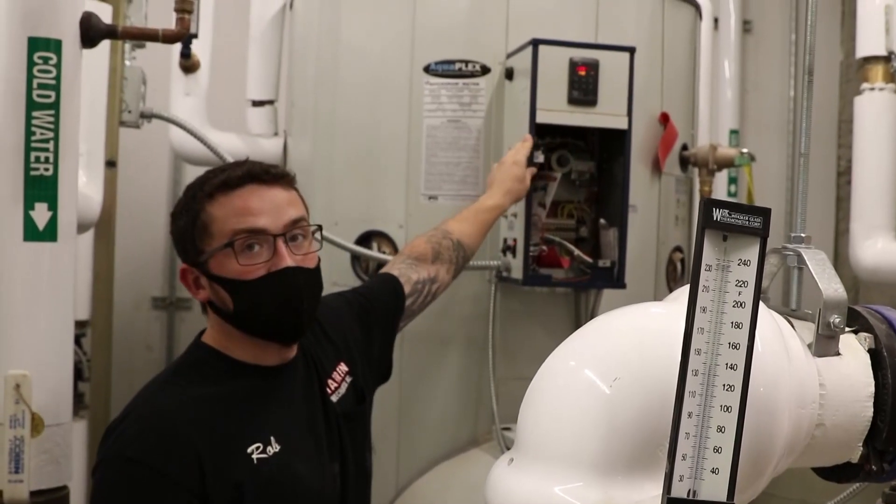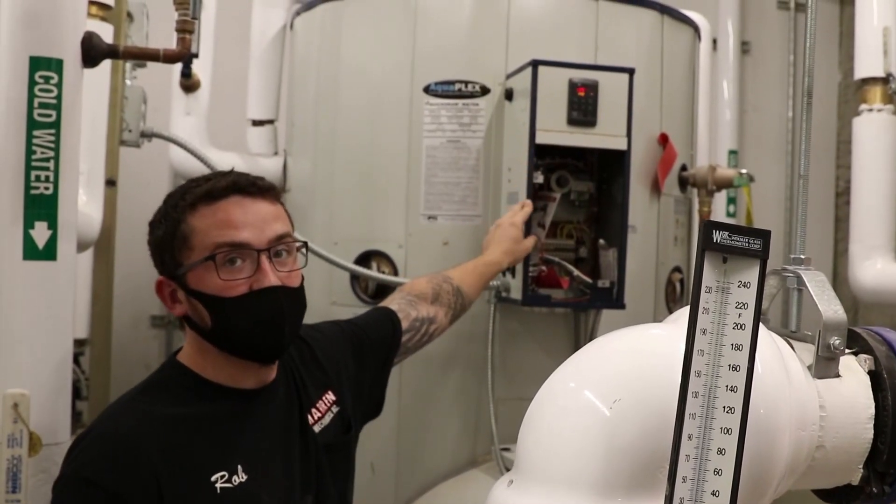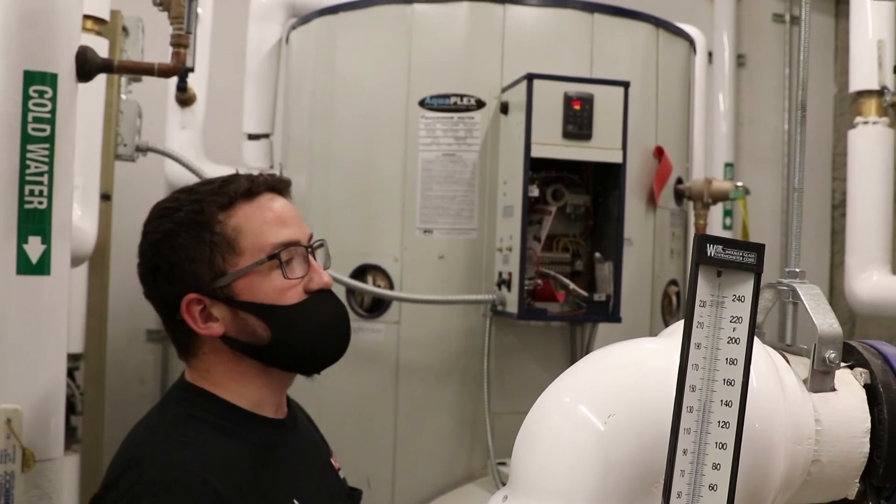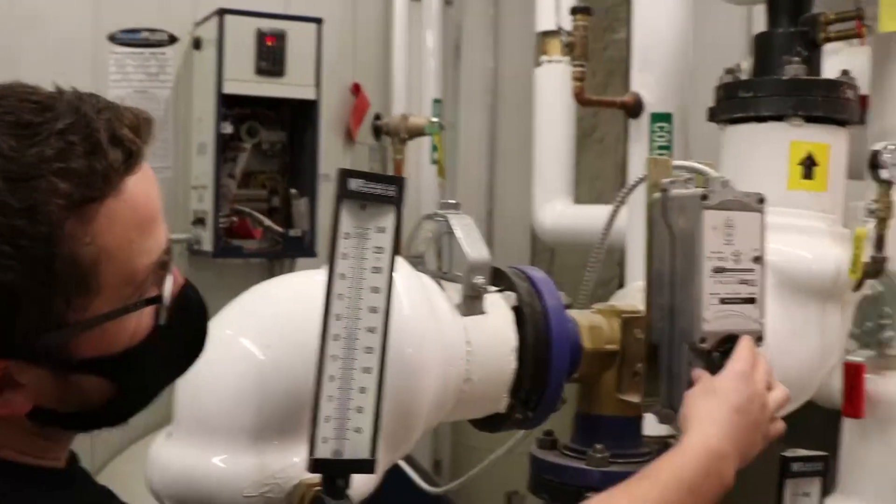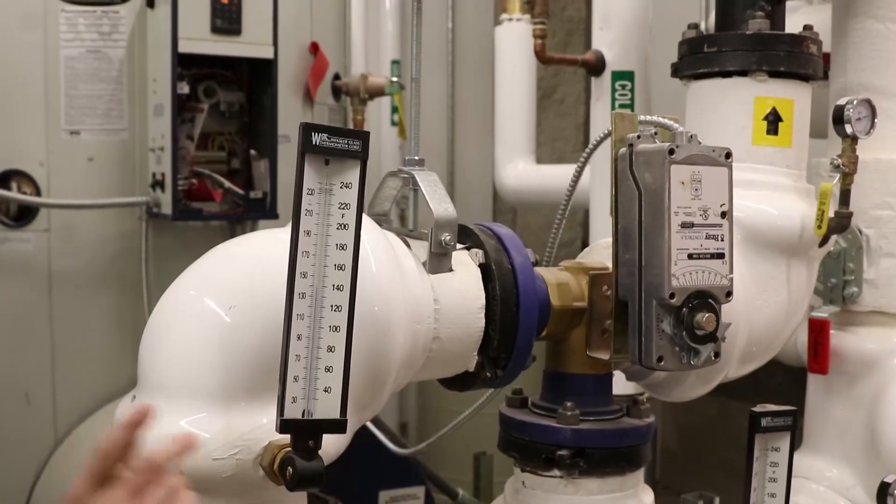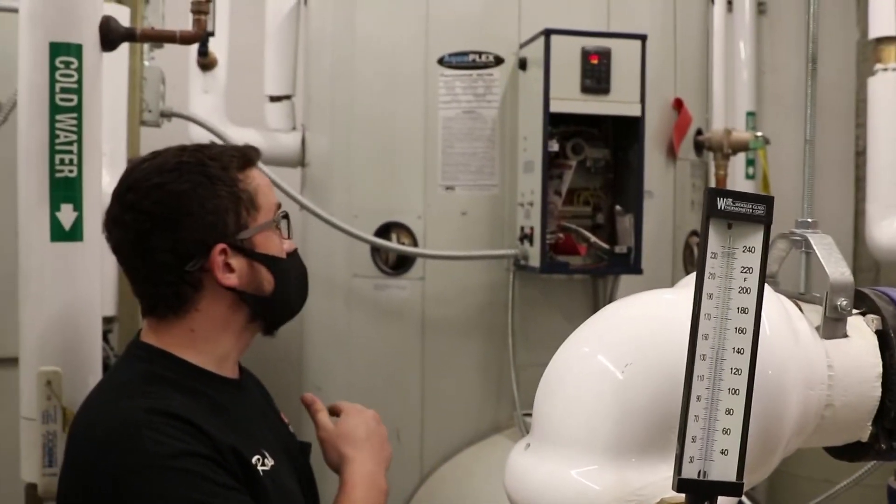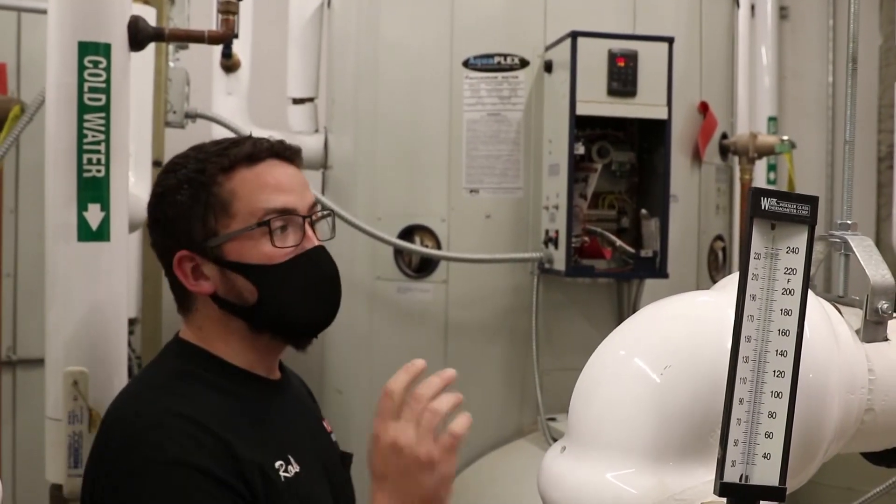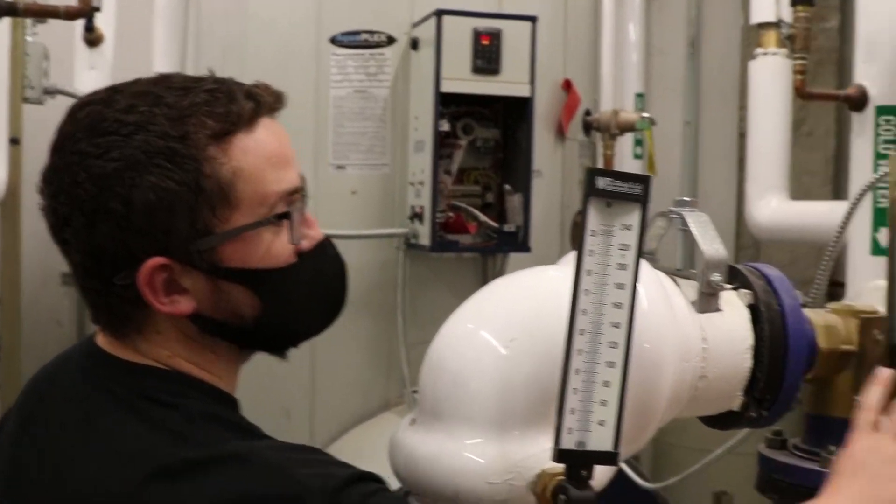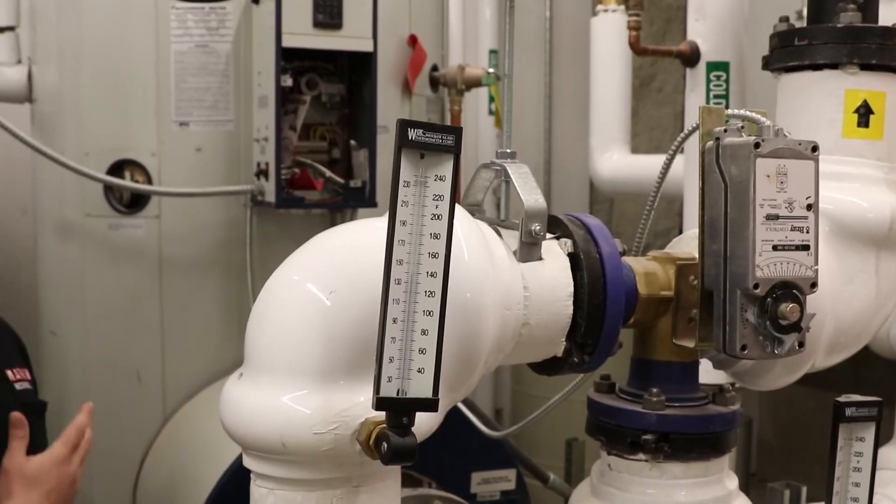When they drop to 135 degrees, a call for heat is initiated. When that happens, this three-way valve will open up to allow boiler water to flow through the heat exchanger. This will happen until the set point is met at 140, at which time this valve will close and it will not open again until there's another call for heat.